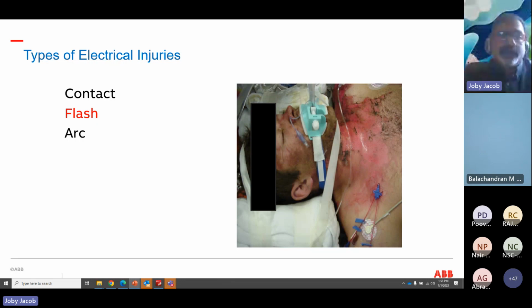So if you are wearing a non arc rated garment in such a scenario, there is a high probability that the burn continues even after the arc flash. Normally the arc flash comes and goes, but you get maximum burns because your cloth gets flashed over and keeps on burning. Particularly cotton, even though it is initially a little bit flame retardant up to 4 cal if it's more than 250 GSM, once it starts burning, keeps on burning and it's very difficult to quench. But if you are using terylene or nylon thread material, it literally melts and sticks to your skin. Then it's very difficult to remove that part also.